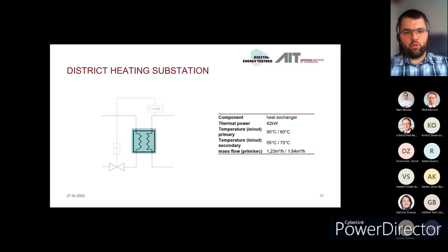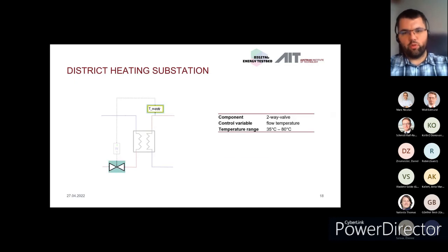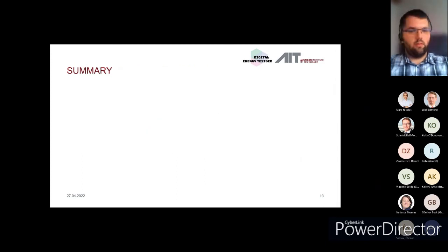The second component which is shown there is the two-way valve, with which we can control, as mentioned before, the flow temperature. And we have tested it between 35 degrees Celsius and 80 degrees Celsius. So in the end, we're now able to control the whole test bench and the district heating substation to represent the building model, and now I have a summary here for you where we can see which are the necessary set points we want to set and which are the necessary measured values the model needs in the end.